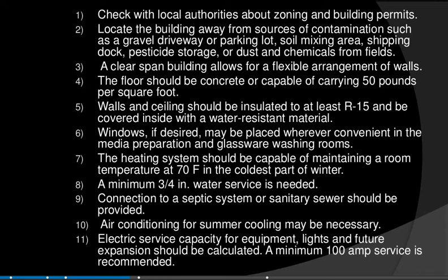The heating system should be capable of maintaining a room temperature of 70 degrees Fahrenheit in the coldest part of winter. A minimum of 3/4 inch water service is needed. Connection to the septic system or sanitary sewer should be provided. As I told you, air conditioning for summer cooling may be optional, but if it is there, so much the better. The electric supply capacity for equipment, lights and future expansion should be calculated. A minimum of 100 amp service is recommended.